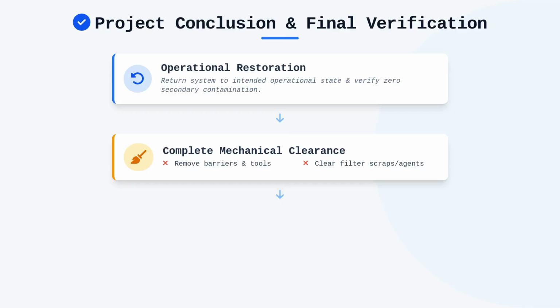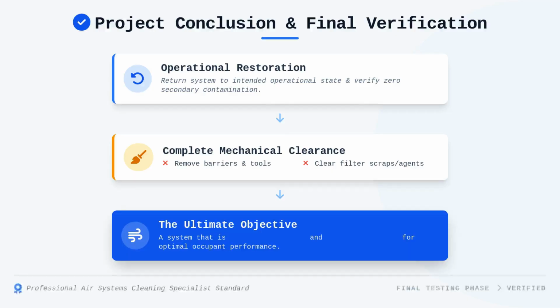A verified clean air system is the result of meticulous planning, disciplined execution, and a rigorous adherence to the verification protocols we have discussed here today. By closing out the project with a thorough final testing phase, you demonstrate a level of professionalism that aligns with the requirements of an air systems cleaning specialist. Your final goal is a system that not only looks clean, but is mechanically and hygienically sound, providing optimal performance for the building occupants.